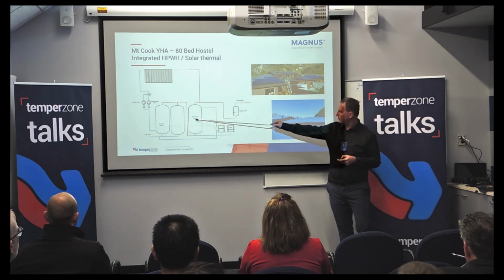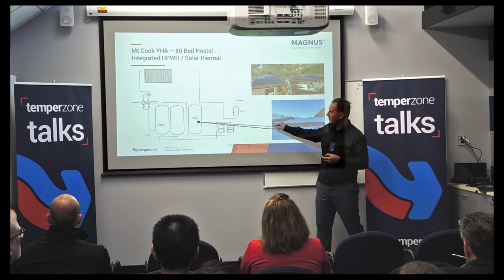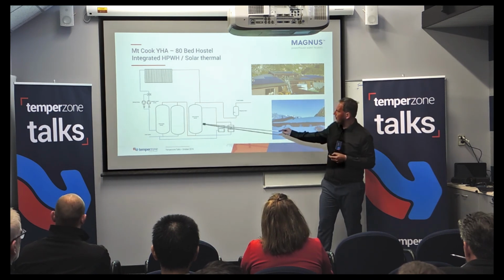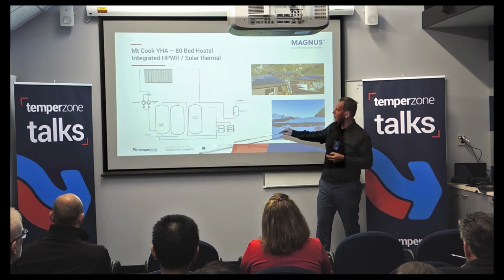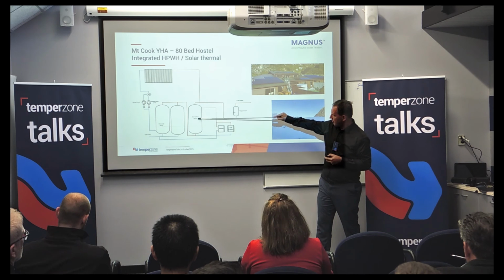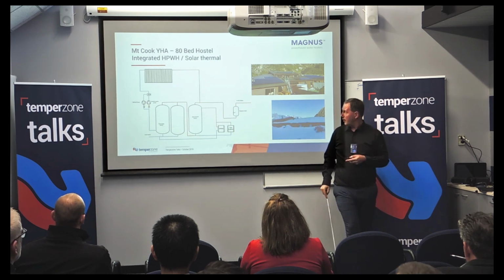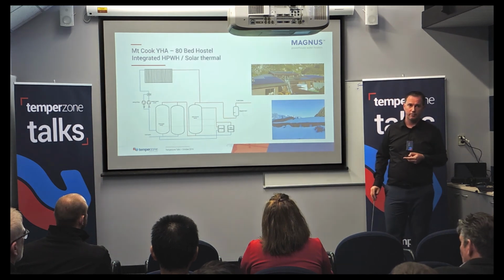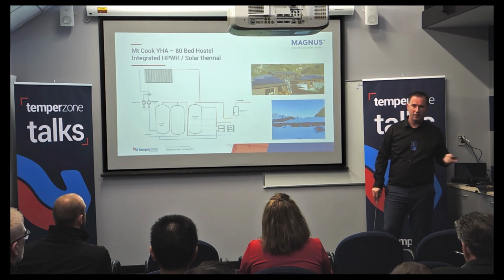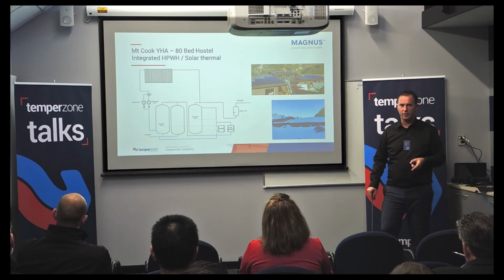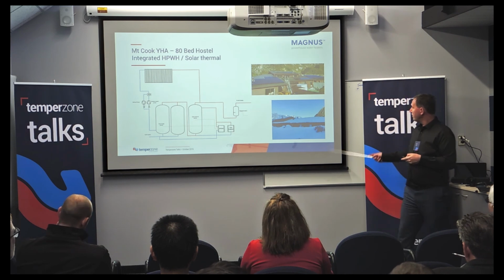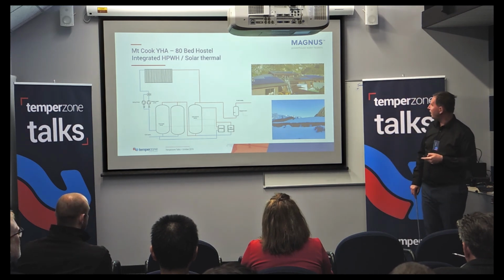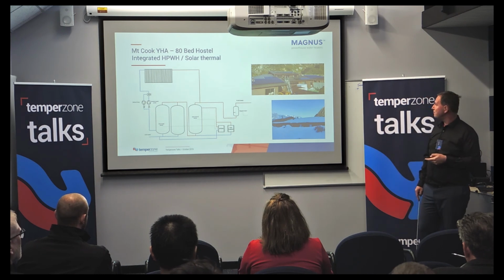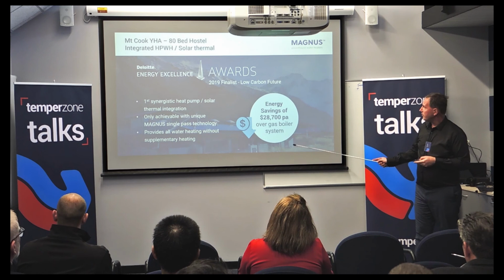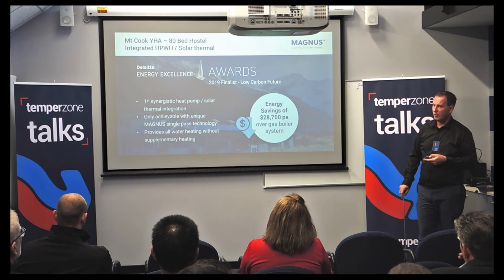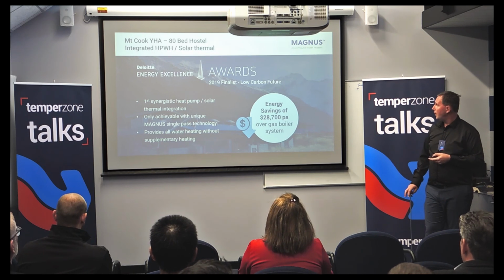So this is the solar hold-off sensor. You start each day with the tanks full of hot water, and then if this tank here becomes cold, the heat pump turns on just enough to heat to this point. Otherwise, it's solar thermal during the day, and around 3 o'clock in the afternoon, the heat pump turns on and does whatever the solar hasn't done. Sometimes we don't get much solar gain, and other times we get quite a lot.